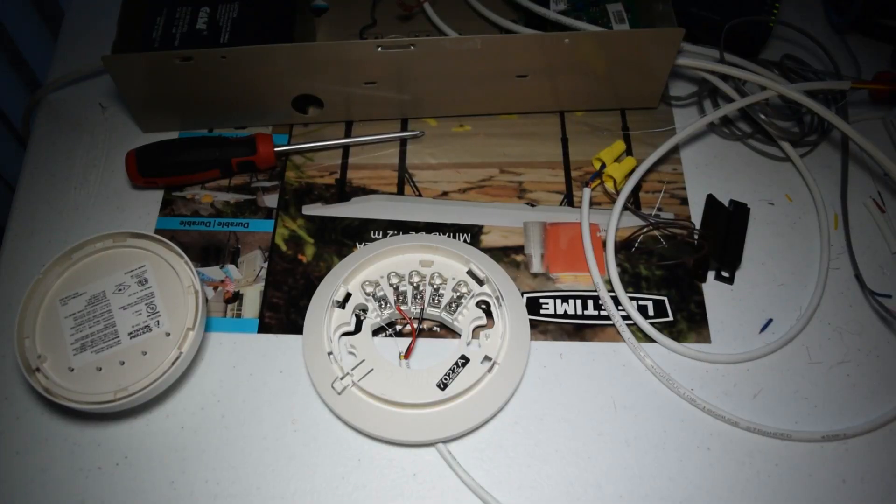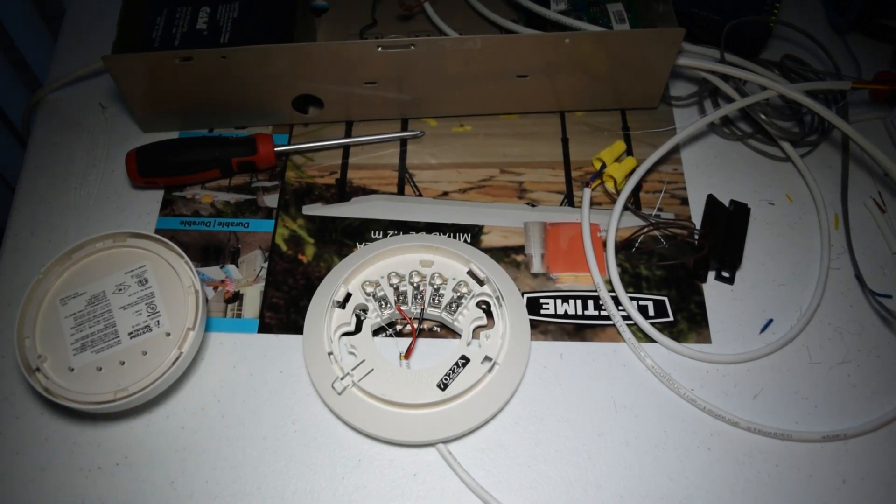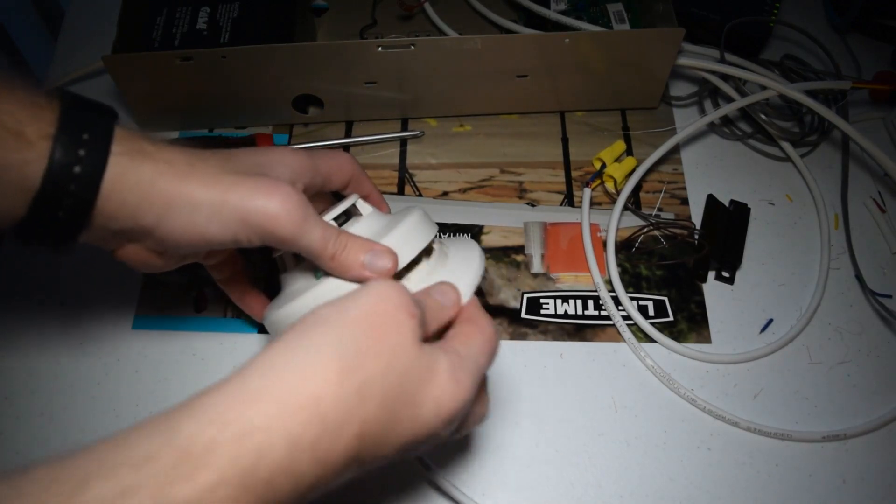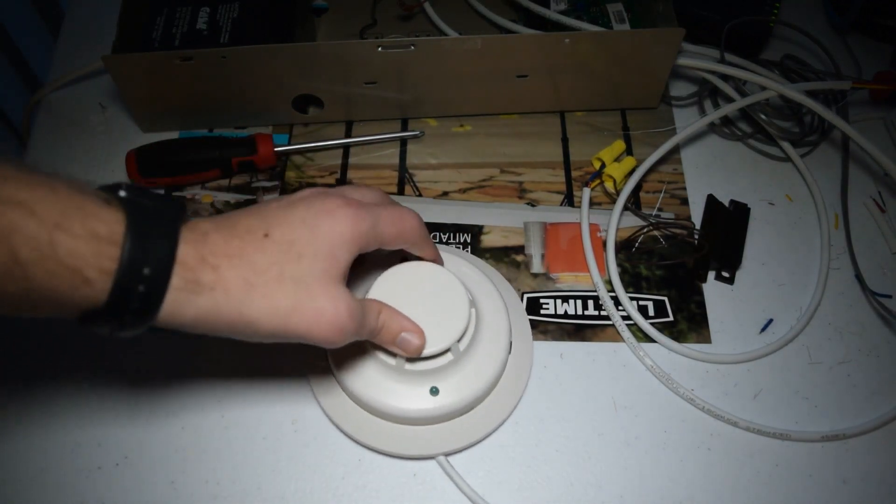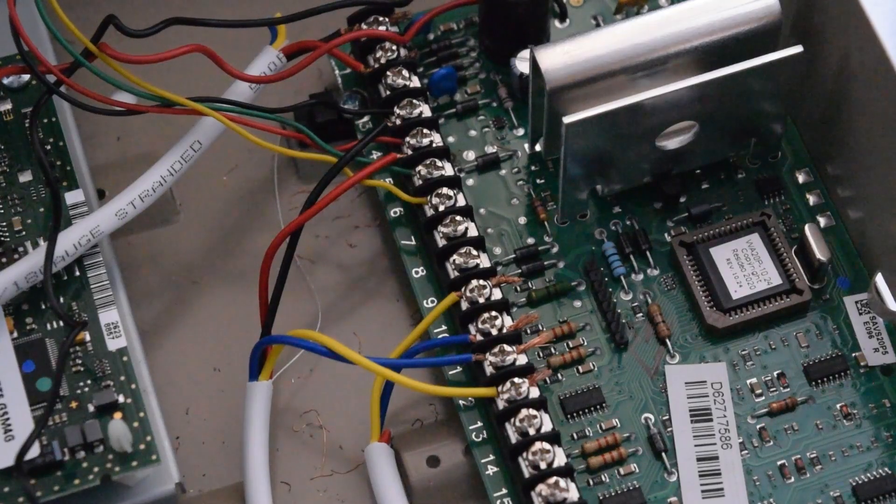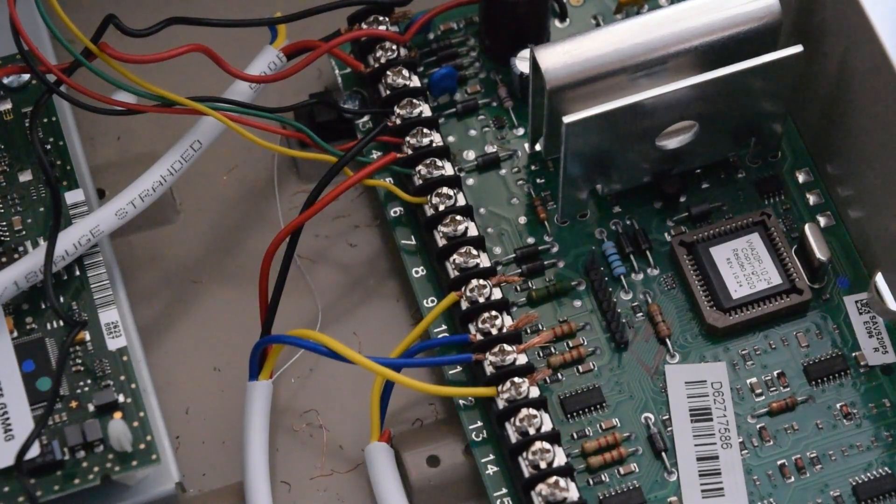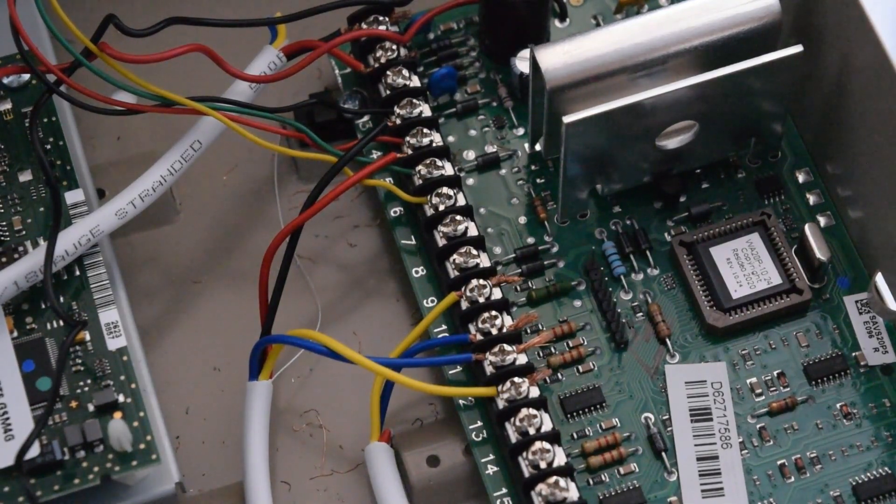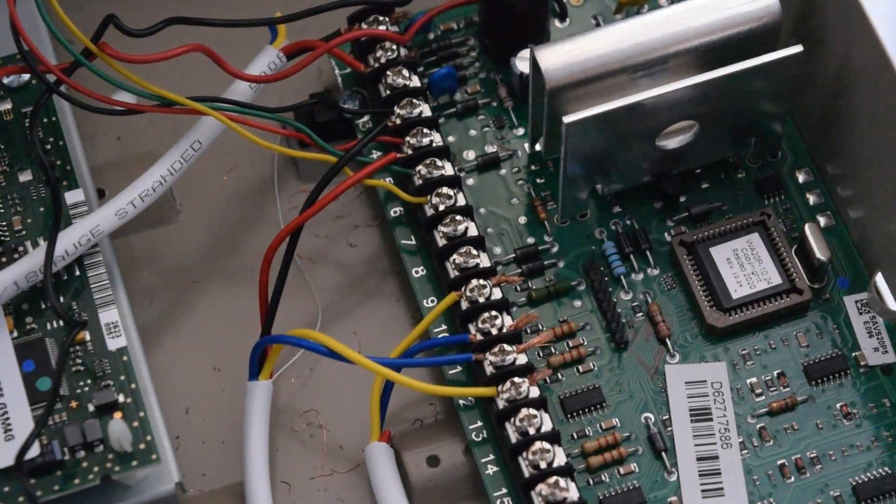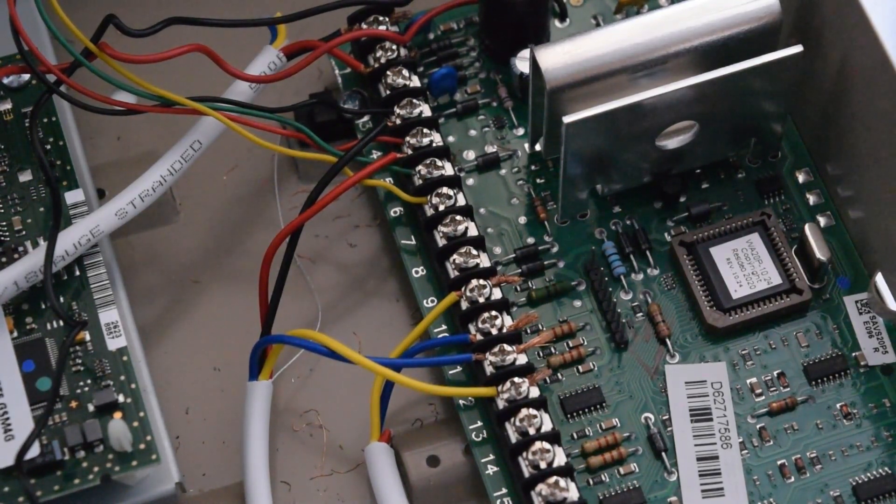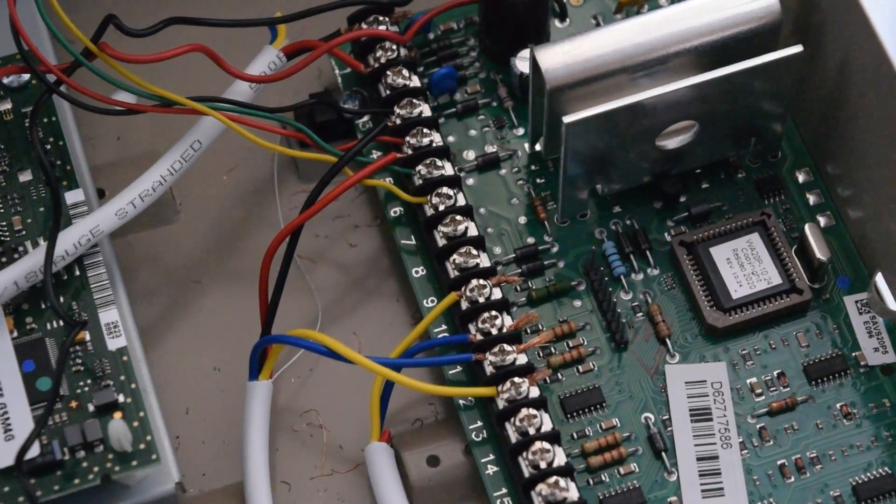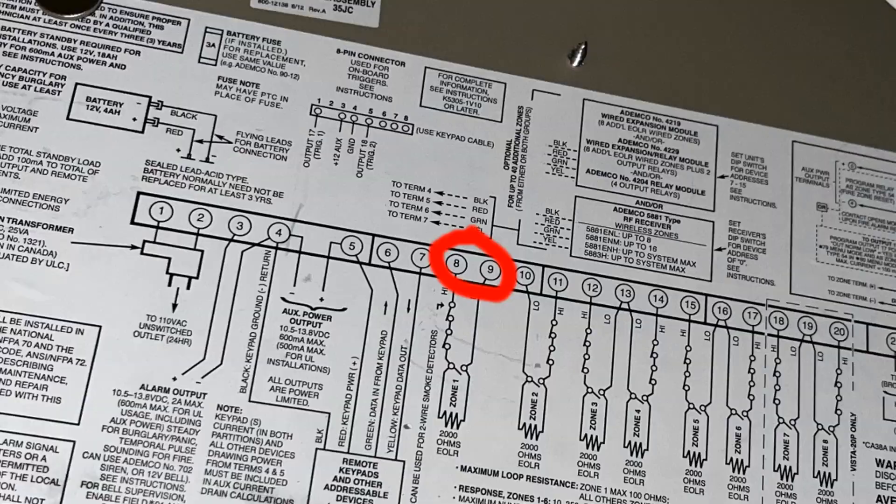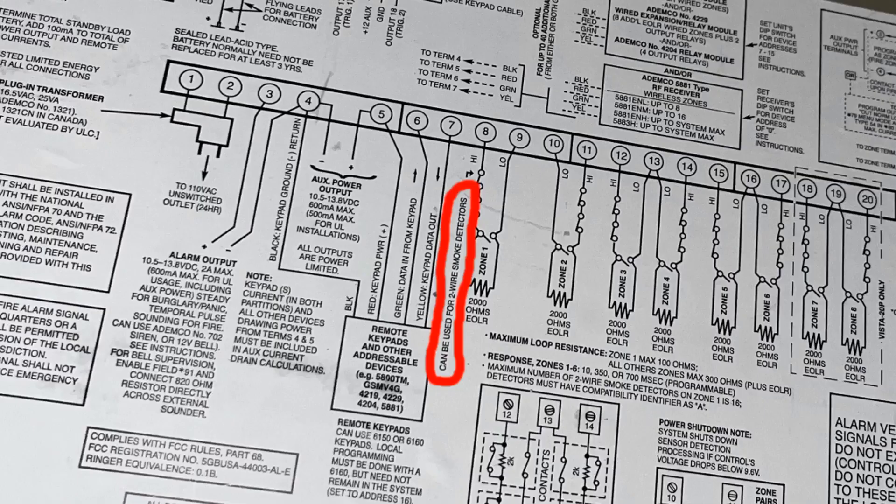So, like I mentioned before, the resistor is going to bridge between the extra positive terminal here and the negative terminal. So I'm just going to put one leg of the resistor into this extra positive terminal here. And then I'm going to put the other leg into the negative terminal. And there we go. We have just officially finished wiring it up. So now that we've finished wiring up the smoke detector side, now all we need to do is just simply put the detector head back on.